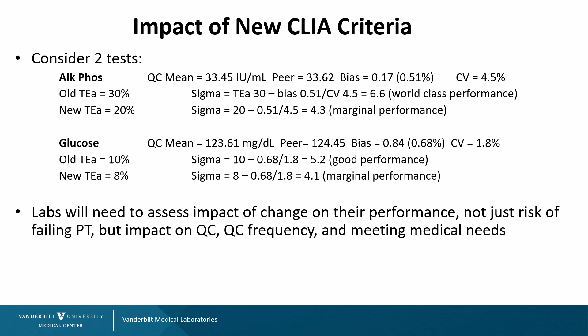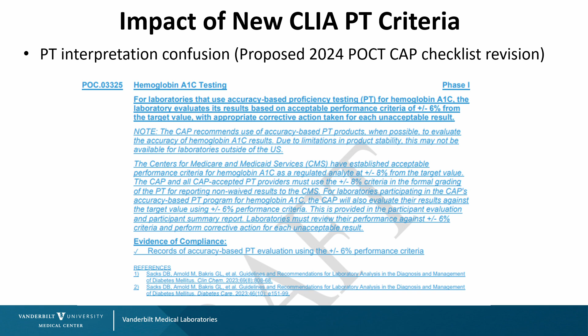And I will say it's somewhat confusing. This is the new CAP checklist. This is going to be coming out later in October, November. And they give two different criteria for performance for hemoglobin A1C. If you were judging against your peer group, which is your methodology, you can use the CLIA limit of 8%. But the NGSP program, the National Glycohemoglobin Standardization Program, is an accuracy target-based program, and they use 6%. So again, you're seeing changes in specifications, and that's going to risk failure if you don't estimate what's going to happen or the impact on your laboratory.